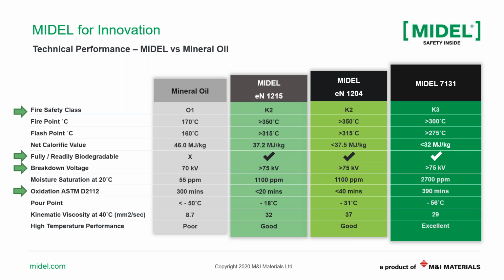Now, this table, I'll spend a little bit more time here because it really shows the key differences between mineral oil and esters. In this table, you see 4 columns. The first one is mineral oil. This is a typical mineral oil values. This next to it is MIDEL EN 1215, which is a soybean-based natural ester. Right hand to it is MIDEL EN 1204, which is a rapeseed or canola-based natural ester. And finally, you have the synthetic ester MIDEL 7131. So you have in this table a mineral oil, a natural ester, and a synthetic ester.